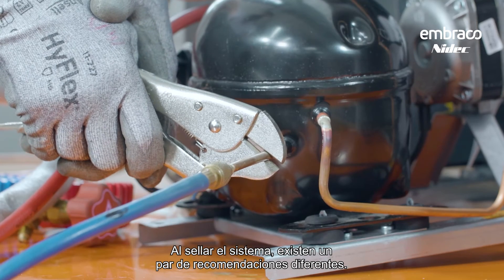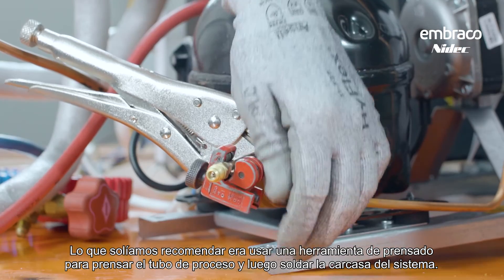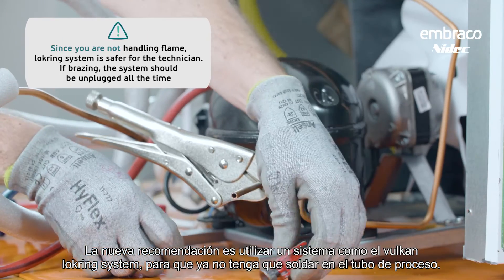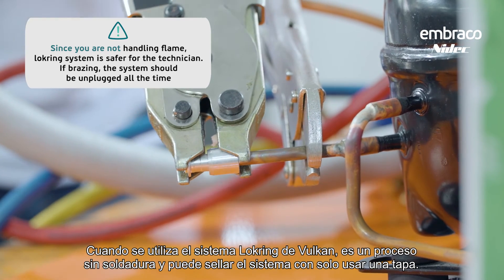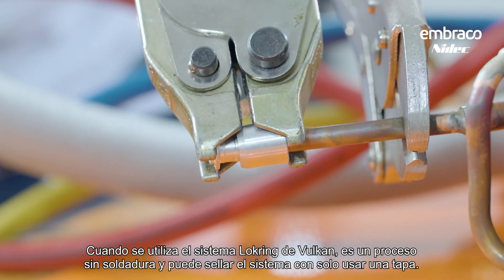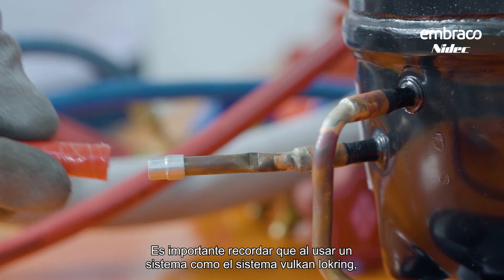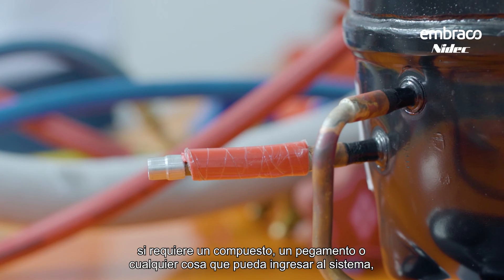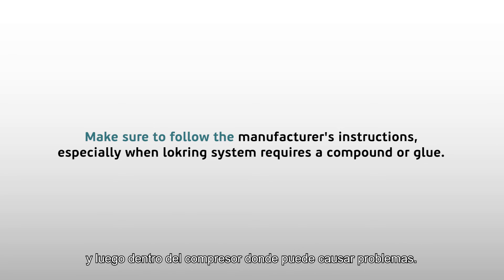When sealing up the system, there are a couple of different recommendations. The previous recommendation was to use a crimping tool to crimp off the process tube and then braze the system shut. The new recommendation is to use a system like the Lokring system so that you no longer have to braze on the process tube — it's a braze-less process and you can seal up the system by just using a cap. When using the Lokring system, if it requires a compound or glue that could enter the system, make sure to follow the manufacturer's directions very precisely so that the compound doesn't end up inside the compressor and cause problems.